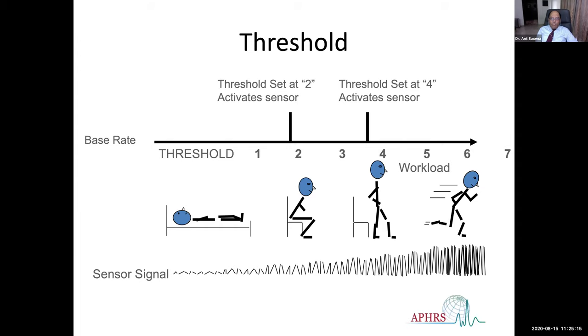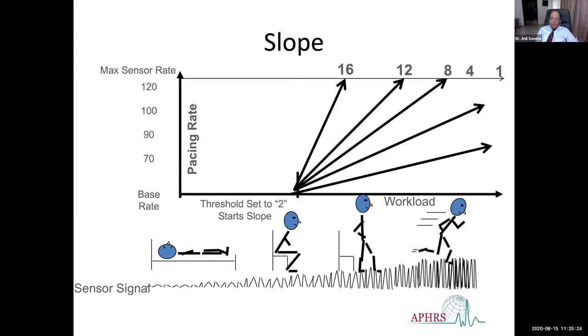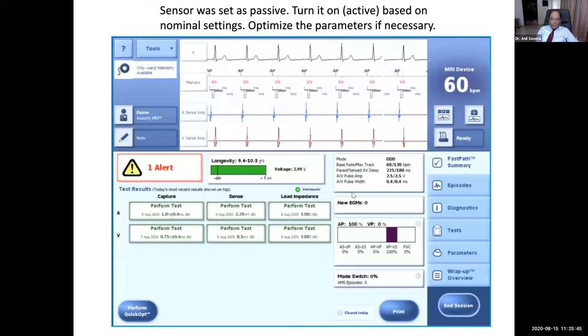We program the maximum sensor detection rate accordingly. The threshold is the activity level at which we want the rate response to kick in - low, medium, or high activity. The response can be made very aggressive or more muted. In our patient discussed earlier, the response was very muted, so we can select a better slope so the response is more aggressive. For the same level of activity, we can have a muted response or a more aggressive one - that's how we program it.